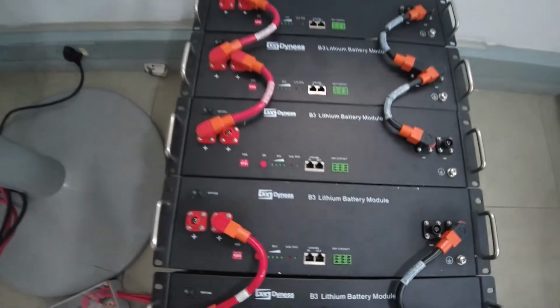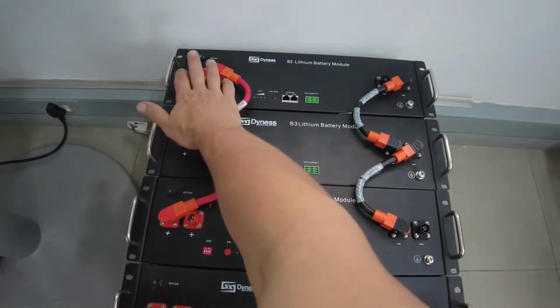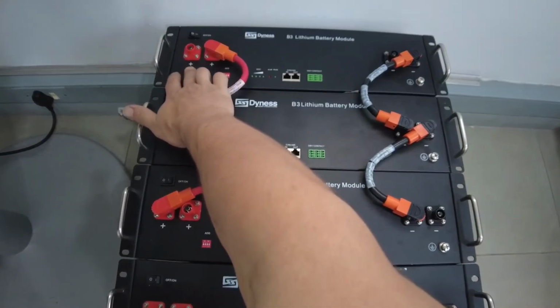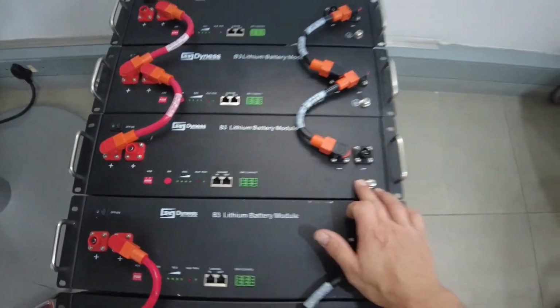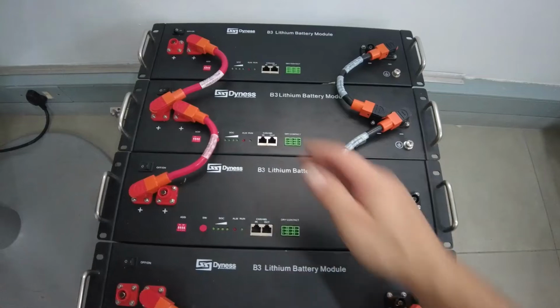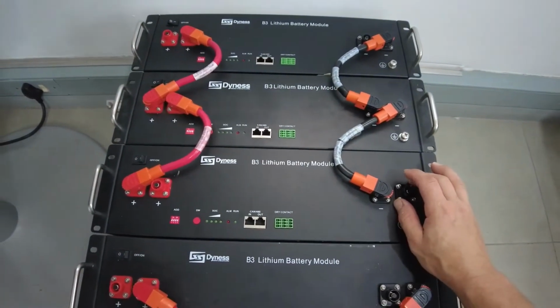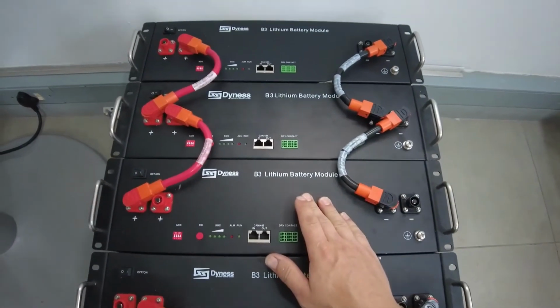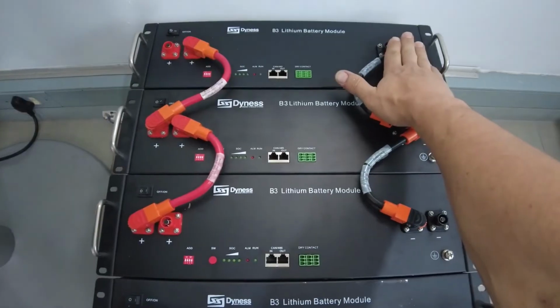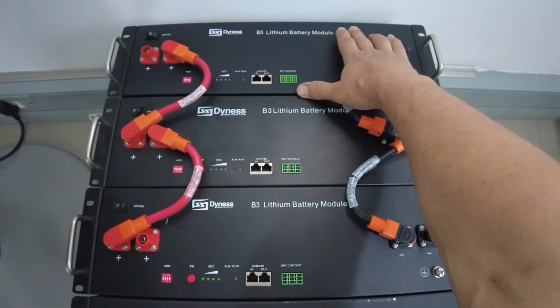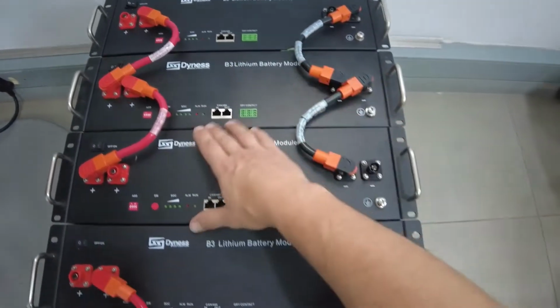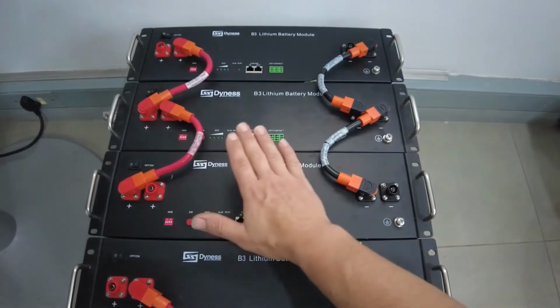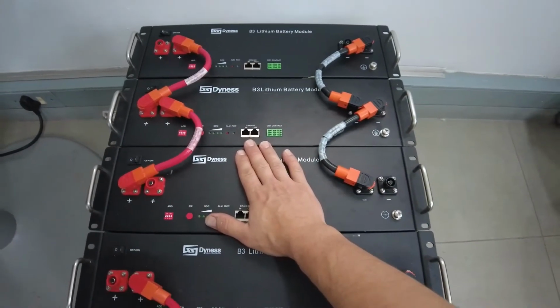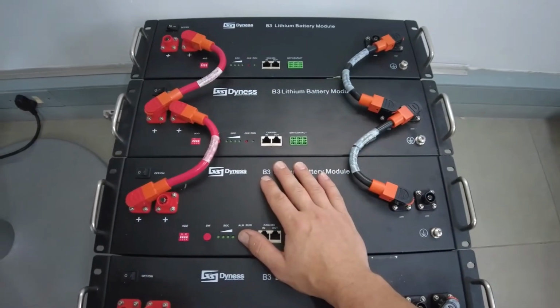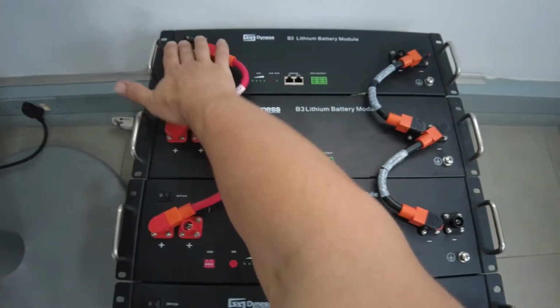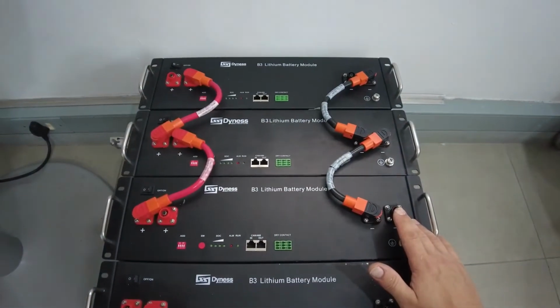So generally, if you have one pair of cables, you will connect the one cable positive to the top, and then your negative you will run to the bottom, and that will evenly charge all 3 batteries, as the positive and the negative from the inverter is across all 3 batteries. If you run the positive and the negative both to the same module, then this battery is going to get maximum charge, the middle a little bit less, and then obviously your last battery even less. So your bottom battery is not being as highly impacted as you will impact the top one. So generally you will always connect from the inverter across all your modules.